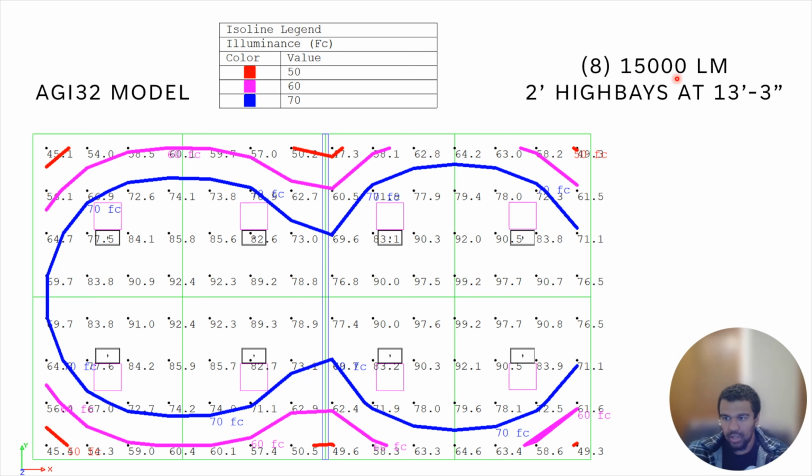I probably could have gotten away with a 12,000 lumen high bay fixture, but I just wanted the 15,000 lumen because it was about the same price for more lumens. Energy consumption wise, each one of these fixtures is about 100 watts. For comparison, a little fluorescent bulb that you're used to, those used to be 60 watts each, so times two is 120 watts. Each one of those bulbs put out about 600 to 800 lumens. So now this one fixture replaces two bulbs with almost 15,000, or 15 times the amount of lumens produced. And that just shows why LED really is so superior to fluorescent at this point.